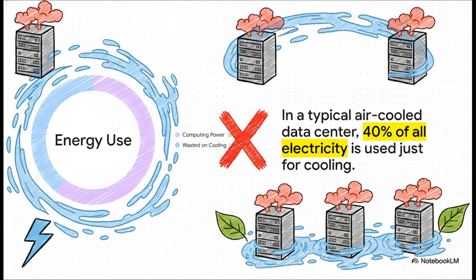So why take that risk? Well, the answer is right here. In a typical air-cooled data center, a staggering 40% of all electricity is used just for cooling. That power isn't doing any computing, it's just wasted on getting rid of heat. That's a huge operational cost and a massive environmental burden. Liquid cooling slashes that waste. So it turns out, the real risk might be not taking the leap.